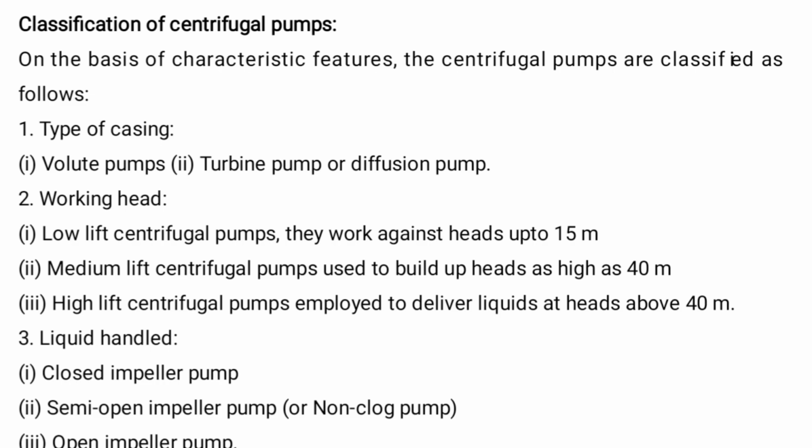Low lift centrifugal pumps work against head up to 15 meters. Medium lift centrifugal pumps are used to build up head as high as 40 meters. High lift centrifugal pumps are employed to deliver liquid at head above 40 meters. Next, liquid handled. Based on the liquid handled: closed impeller pump, semi-open impeller pump, open impeller pump.